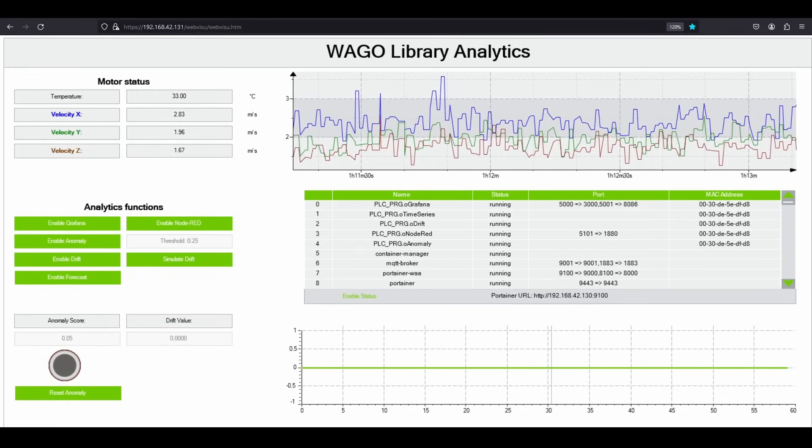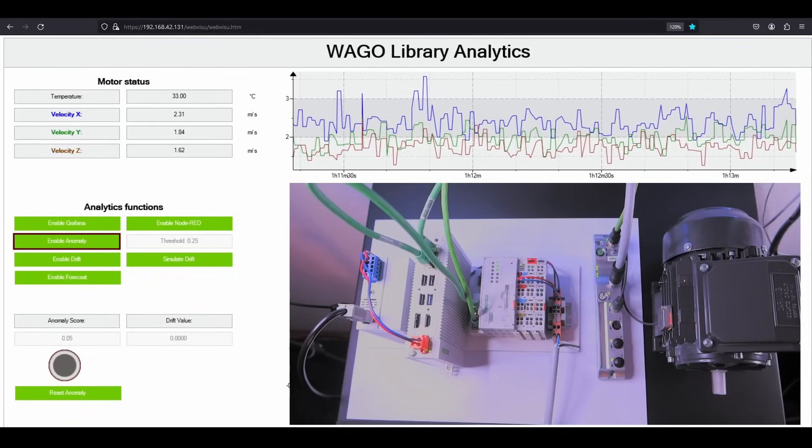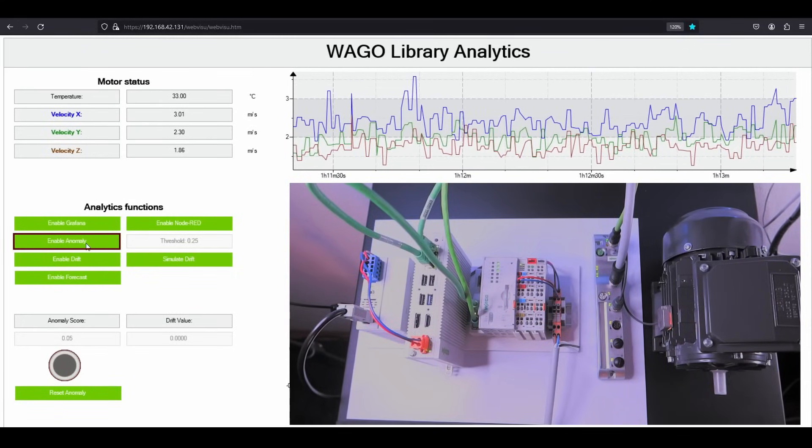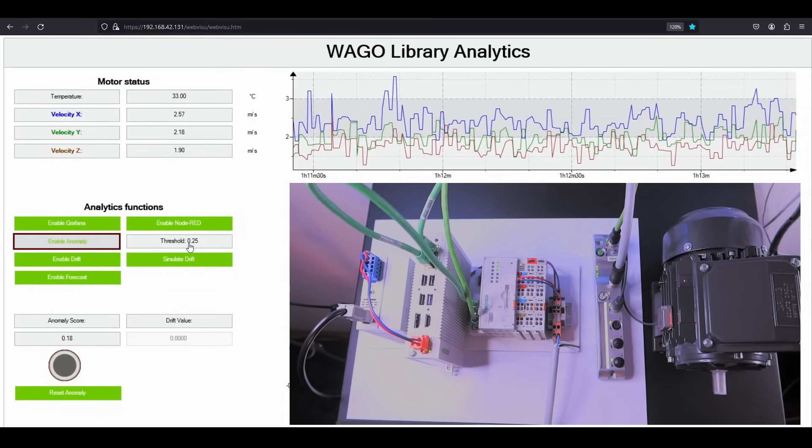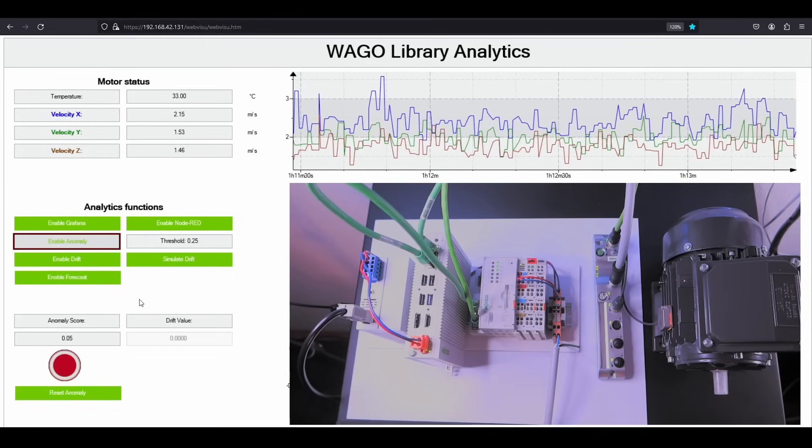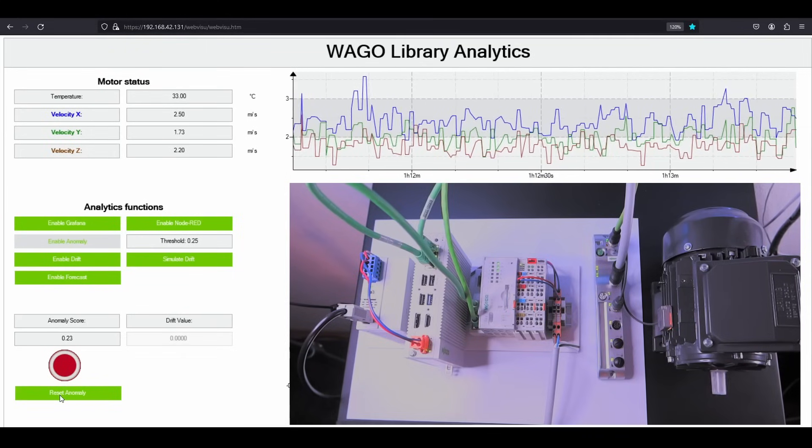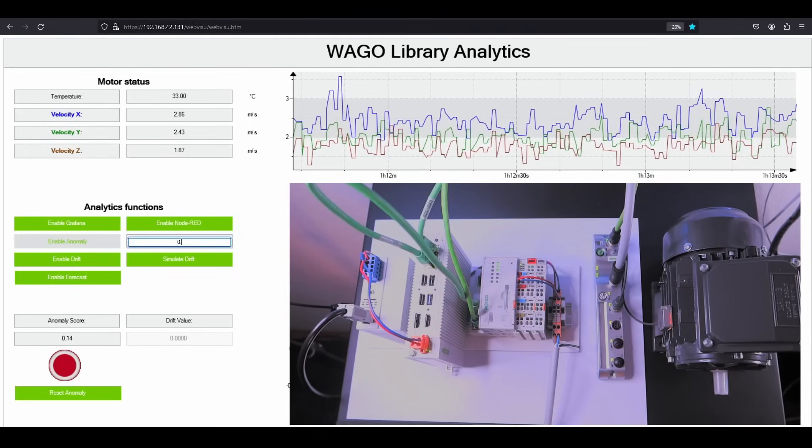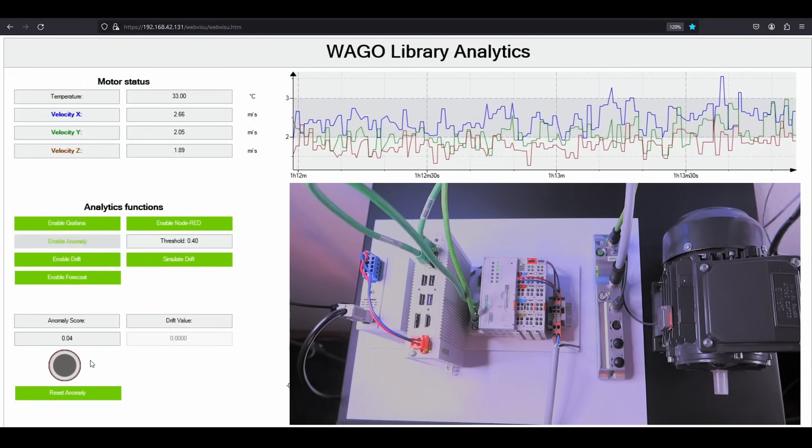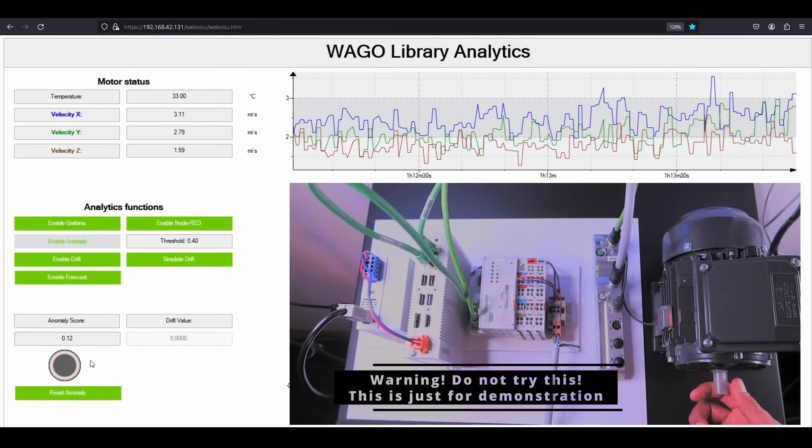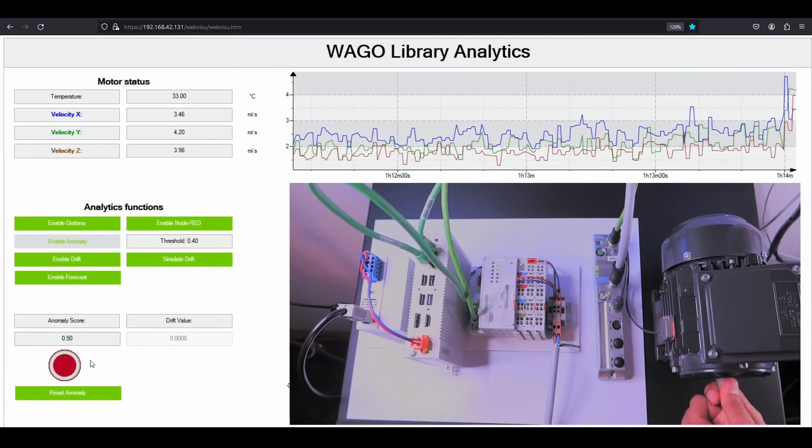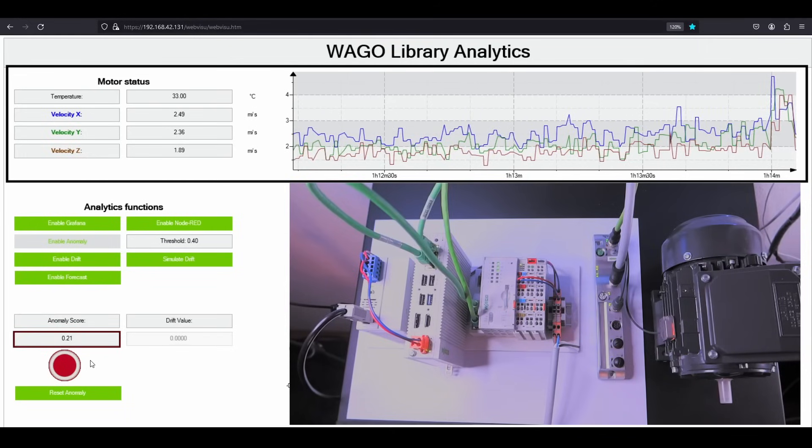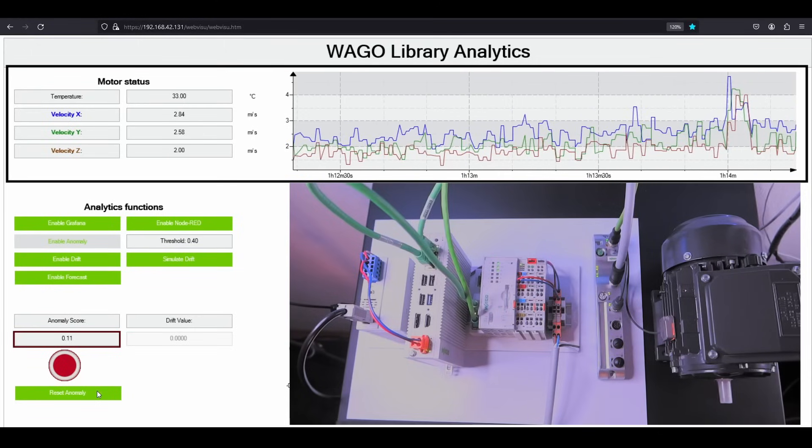To start with anomaly detection, I just have to enable it using this button. This will begin pushing the motor vibration data values to the Docker container responsible for anomaly detection. The threshold is set to 0.25 by default, and we can see an anomaly has already been detected because the anomaly score is higher than the threshold. Let me change that to 0.4 and reset the anomaly. Now you can see the anomaly score is below the threshold. Let me introduce some sudden change in the motor, which I can do by holding the shaft to introduce some vibrations. You can also observe the changes in vibration data on the graph. There we go. The anomaly score was higher than the threshold, and hence we have an indication again.